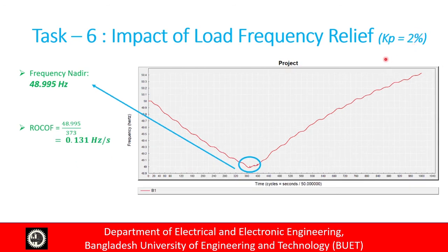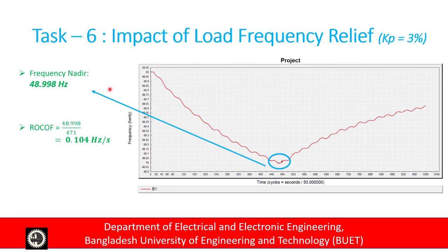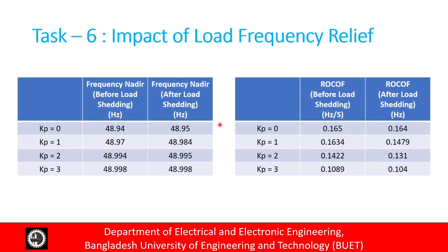For kp equal to 2%, the frequency nadir is 48.995 Hz and the RoCoF is 0.131 Hz/s. For kp equal to 3%, the frequency nadir is 48.998 Hz and the RoCoF is 0.104 Hz/s. We can see that as kp increases, both the frequency nadir and RoCoF improve. Comparing the system before and after load shedding, both frequency nadir and RoCoF values have improved after load shedding. That concludes the presentation for this project — thank you for your patience.